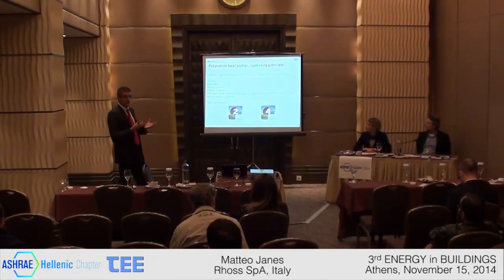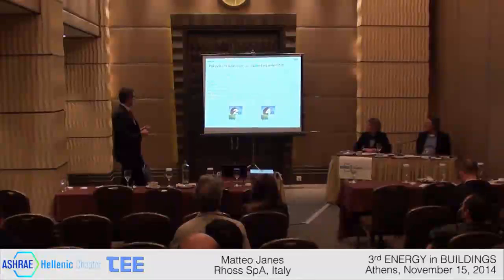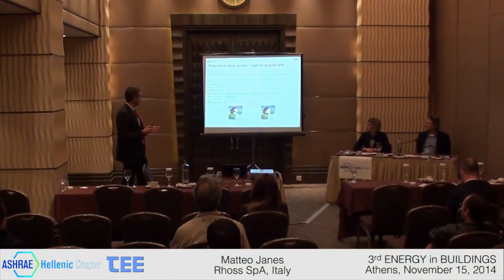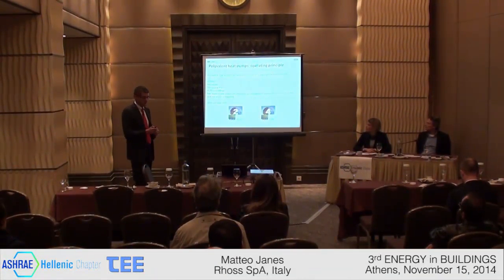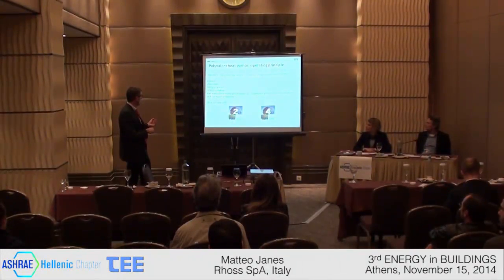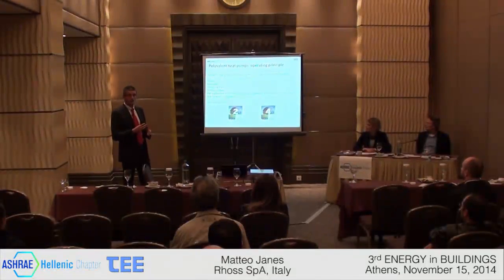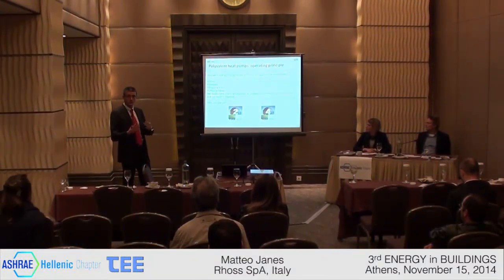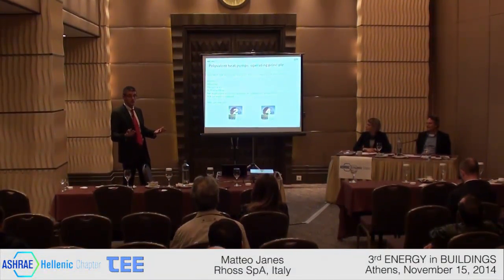What is the typical application of this technology? Well, polyvalent heat pumps can be used in 2-pipe and 4-pipe systems, which means hotels, hospitals, shopping malls, office buildings, but in general all applications where simultaneous or independent production of chilled water and hot water is required. Even process cooling or industrial applications could be served as well.